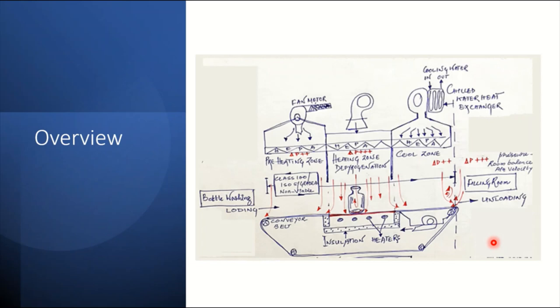Let's understand what qualification studies are required. We talk about the conveyor, the HEPA where air is coming through, claiming this is ISO 5 grade area. We talk about pressure differentials and airflow patterns. Qualification is very fundamental. We should understand what actually we need to depyrogenate, how we challenge that, and what attributes are controlling the depyrogenation—obviously temperature. There will be a heater bank, a blower, and the area should be maintained as ISO 5, so the filter should be integral.